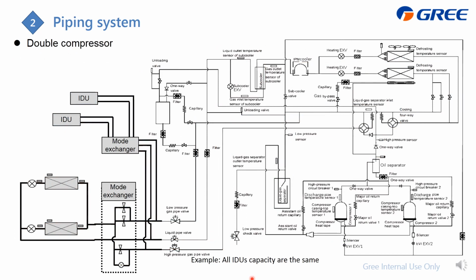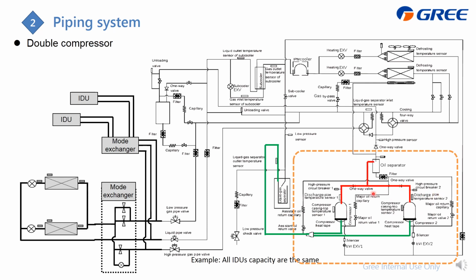As for more complicated 2 compressor models, the difference is only this part. We just make it to be 2 compressor model, and also the gas from the gas liquid separator is divided into here, and then we send the refrigerant to these 2 compressors. And then at the discharge, we also combine them together to send the refrigerant to the oil separator. And also the oil from the separator, we also divide it into 2 parts for the major oil return. As for the assistance oil return, also send it to here, it's okay.